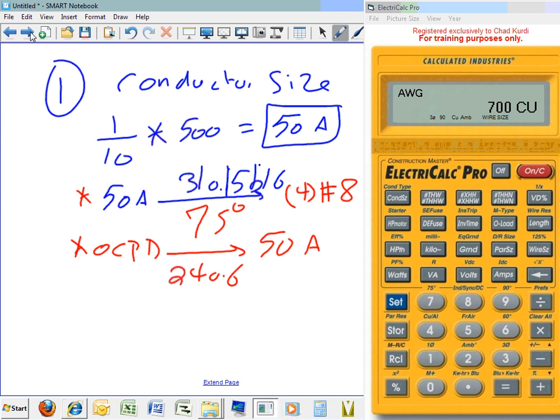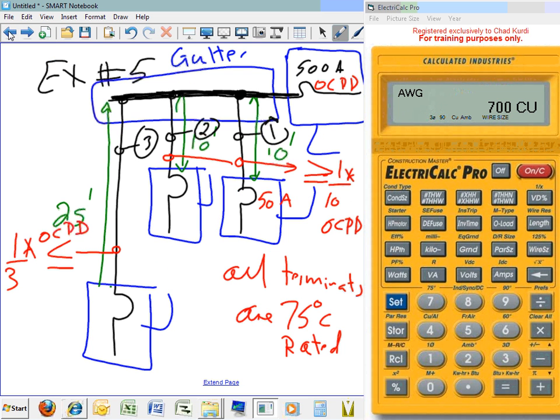Okay. Now knowing this, that's the minimum. Here's what I want to change slightly, guys. So the minimum is 50, can I tap 100 amp? I'm going to put 100 amp here. Is it okay to put a 100 amp conductor from this system? Yes, because 100 is more than 50, so whatever conductor I size here is always more than 50. For this one, just to spice it up, I decided, based on that minimum overcurrent protection device and cable I can put here, that I really want a 100 amp disconnect. So I put 100 amp.